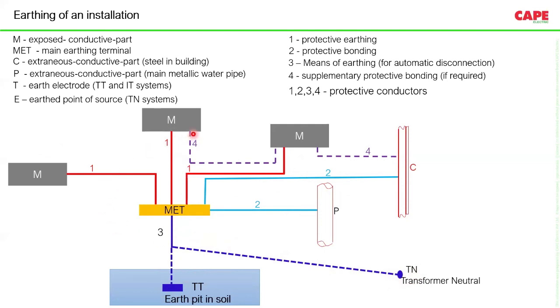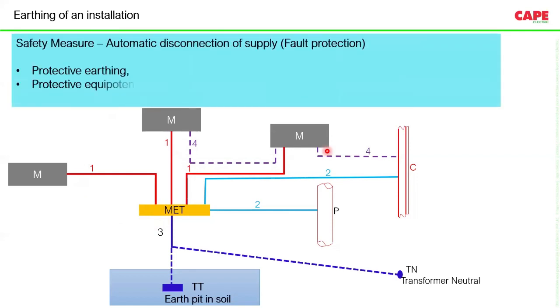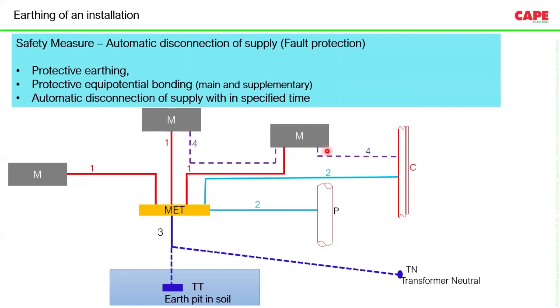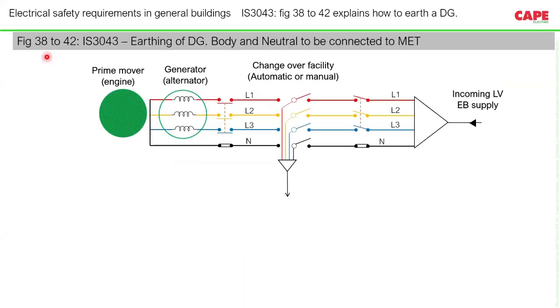What is required extra in a medical location is number 4, which is called supplementary equipotential bonding. So this picture is also included in the NEC, and near to that, a lot of explanations are given. Please go through it. So earthing is called protective earthing, protective equipotential bonding, which consists of main and supplementary equipotential bonding, and automatic disconnection of supply within the specified time. If this safety measure is properly implemented in a hospital, the chance of fire from whatever reasons, especially air conditioner or fire from the medical locations, can be almost nullified.